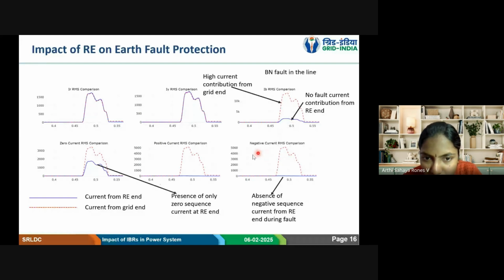And we can see the negative and zero sequence components also. The negative and zero sequence components are also present only from the grid end. The grid end is having this zero sequence current, positive sequence current, negative sequence current, all the currents. Whereas the RE end is having only the zero sequence current, which is getting reflected in R, Y and B of the RE end, not on the grid end. So this is the thing that we are observing.